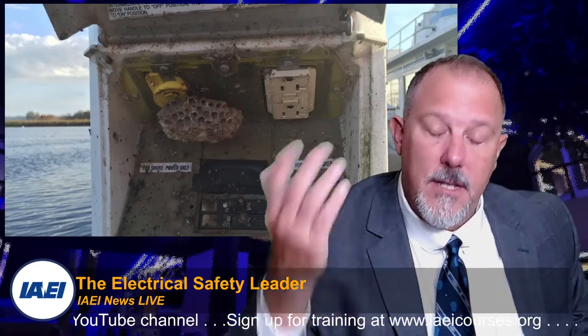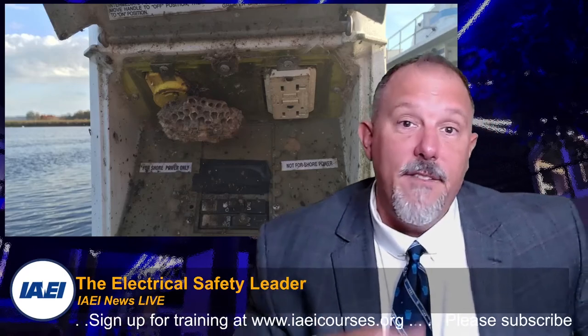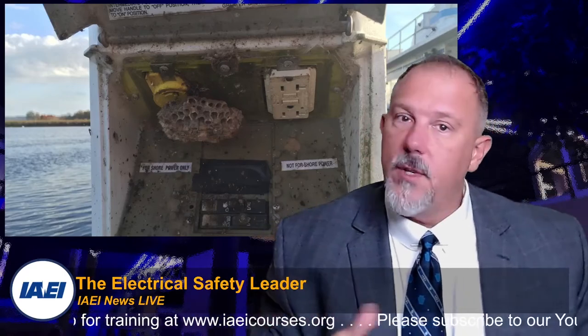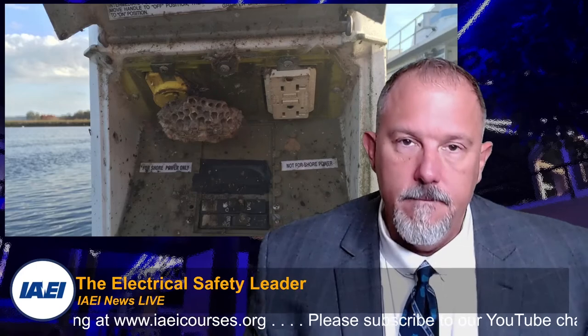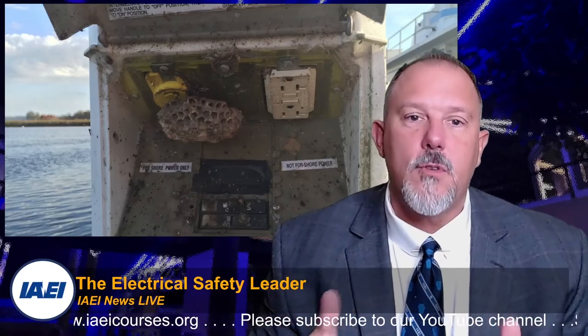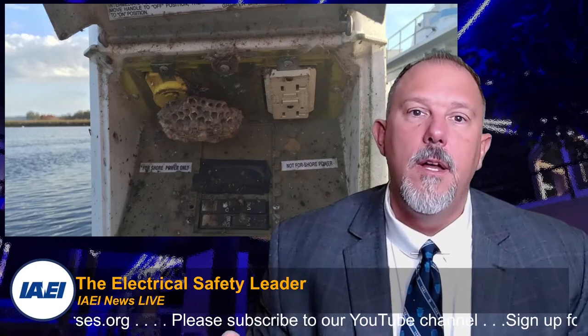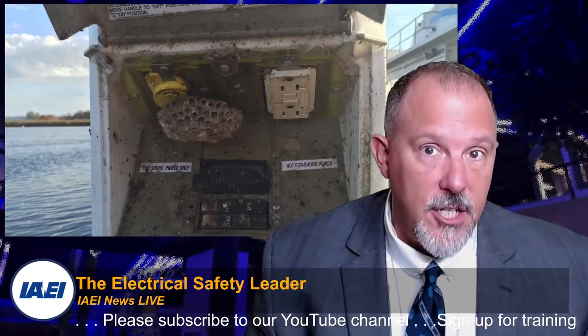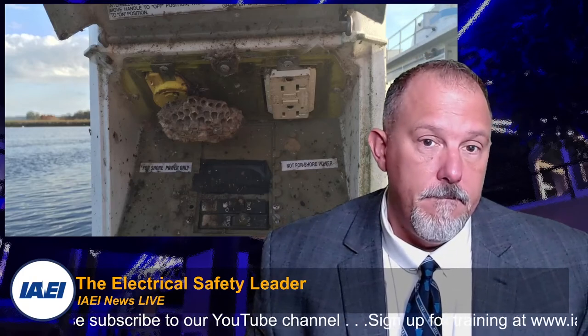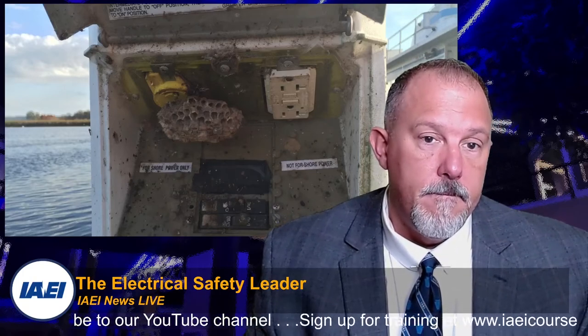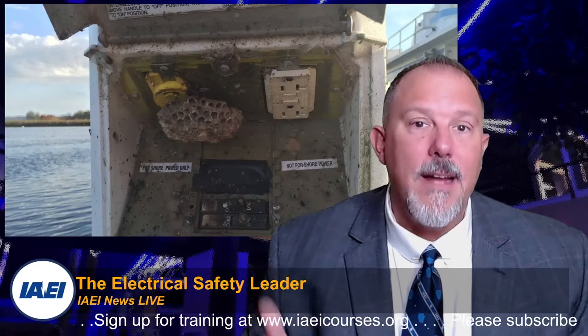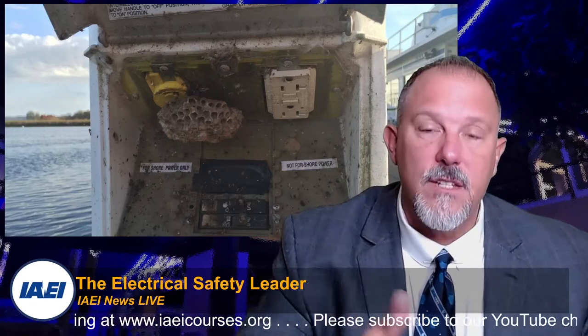The inspection that I was helping with on this case, every one of these doors we opened was a new experience. Over 90% of the receptacles we tested were providing power but were not providing GFCI protection. In this type of condition, this type of environment, we cannot expect these devices to last forever.